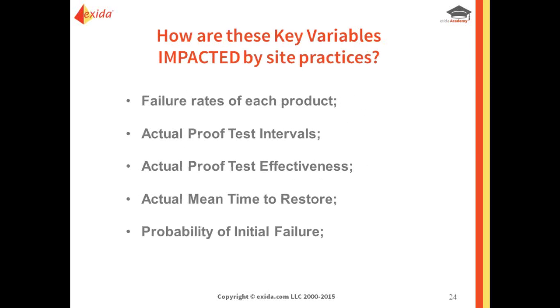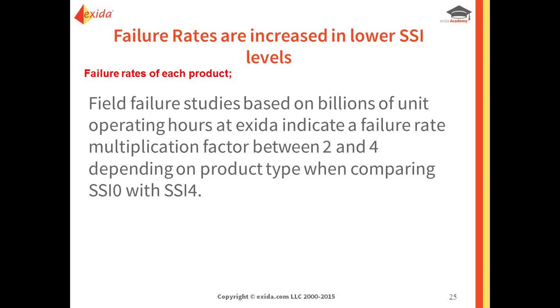So now, how are these key variables that we talked about impacted by the site? Well, first you're going to have failure rates. They're going to be different on each product. Actual proof test intervals will change. The actual effectiveness of that proof test will be different. Your mean time to restore will not be the same from site to site, and the probability of initial failure will change. So now let's go into each one of these and give an example of what we have found.